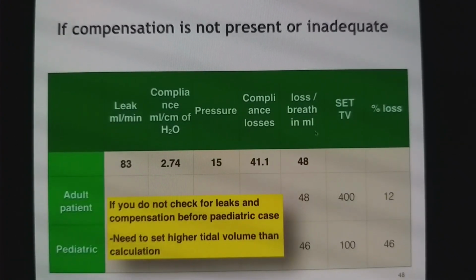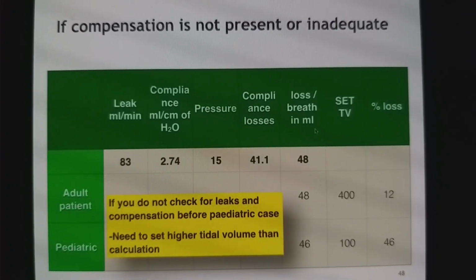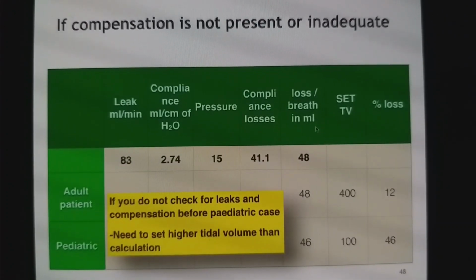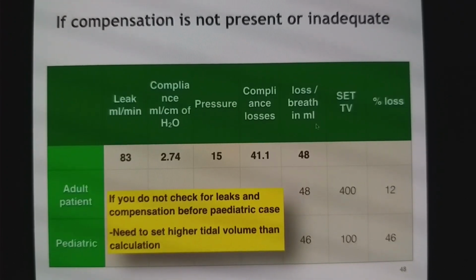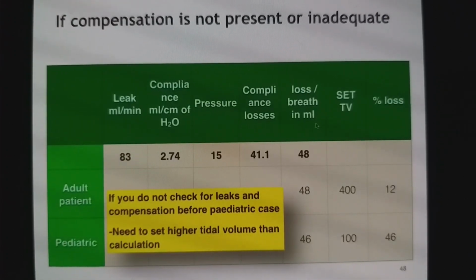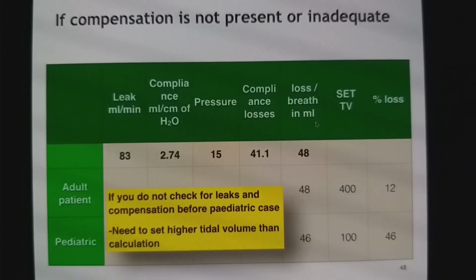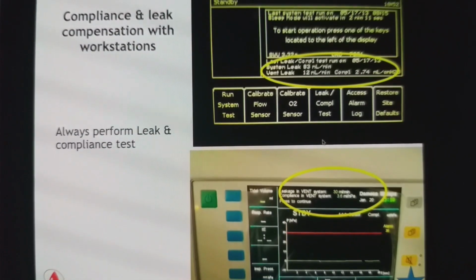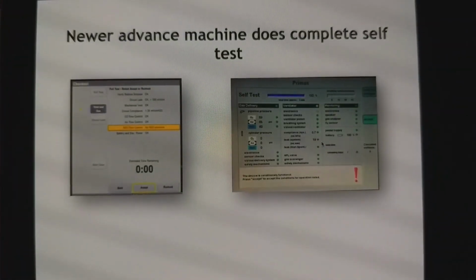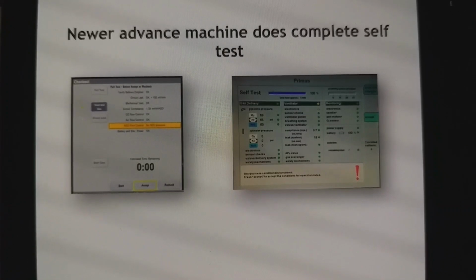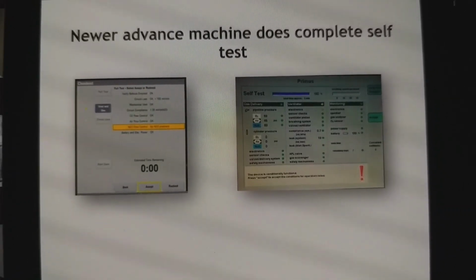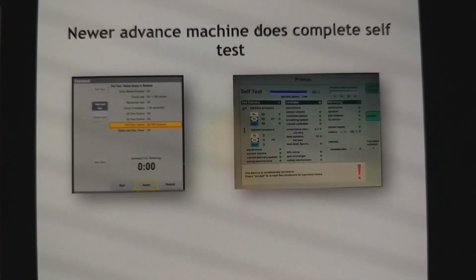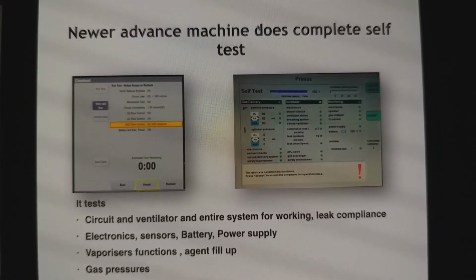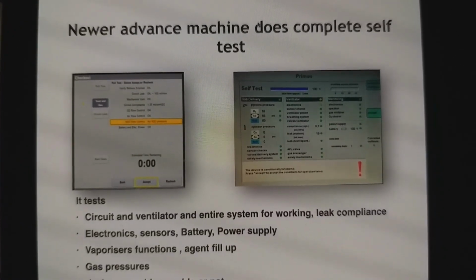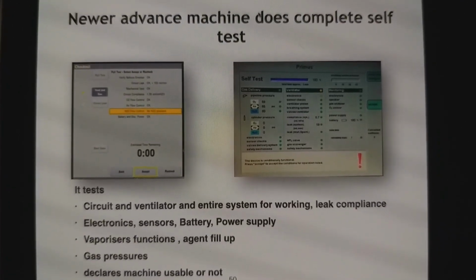So believe me, it is always proper to check for leak and compliance once you change the circuit. For an adult patient or for a pediatric patient, the moment you change the circuit, you should again test that circuit for leak and compliance. So always perform the leak and compliance test. In fact, newer advanced anesthesia machines have come out with a large number of tests. They test the circuit, ventilator, leaks, entire system, electronic sensors, battery, power supply, everything.